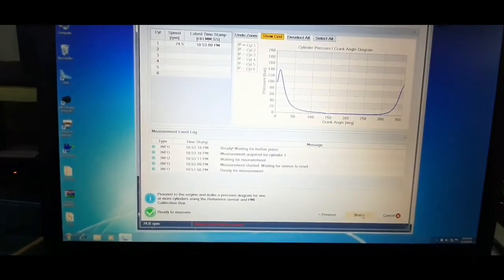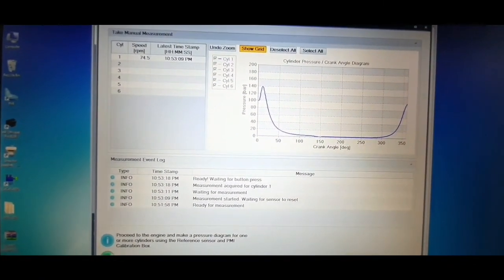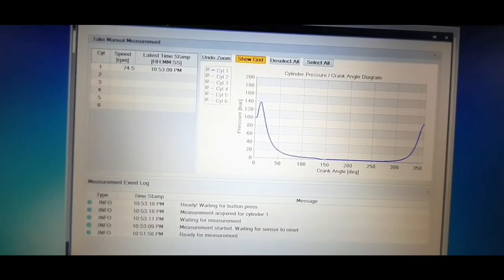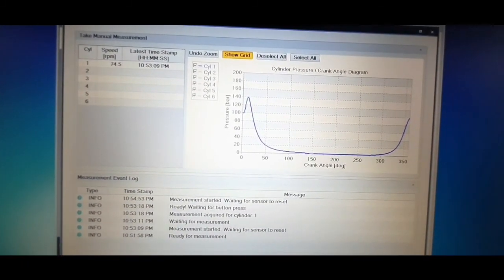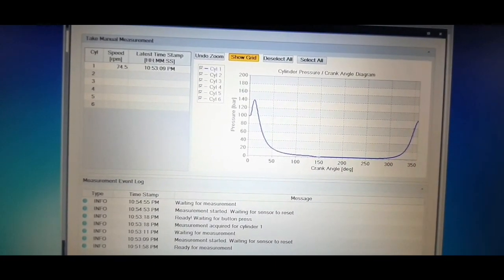A pressure versus crank angle diagram of the respective unit will be displayed on the screen. Now shut the indicator cocks and disconnect the transducer, and move to the next unit and follow the steps as explained earlier.